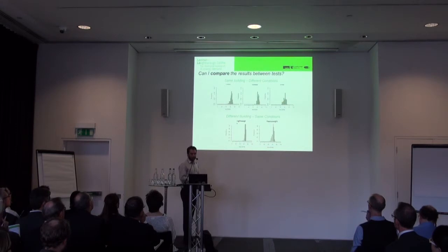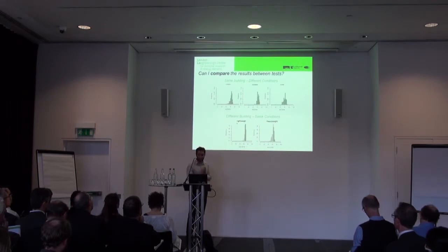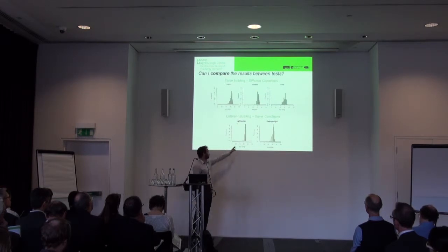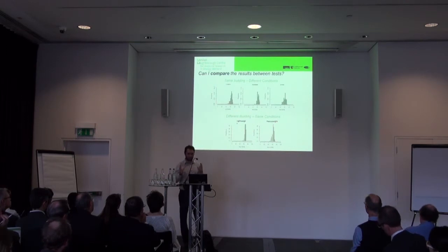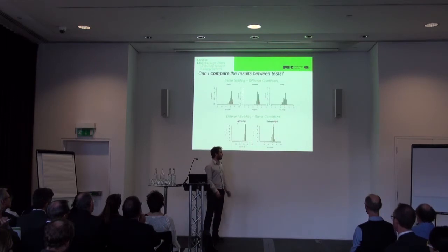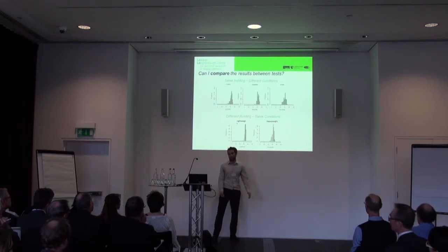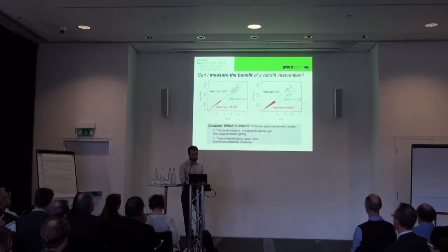The second thing we'll look at is, what if we have the exact same weather conditions, but we're testing different types of buildings. What I'm showing you here is a lightweight and a heavyweight building, which are identical in every single way, other than the fact that one's lightweight and one's heavyweight. We can see the distribution of results, the measured heat loss. The lightweight building is quite a tight distribution, small and narrow. That's not the same with the heavyweight building. So if we were testing the heavyweight and the lightweight building right next to each other under the same weather conditions, we might expect a nice reliable result for our lightweight building. We might actually be getting an underestimate for our heavyweight building, which means it's very difficult to compare the two with any sort of fairness at all.